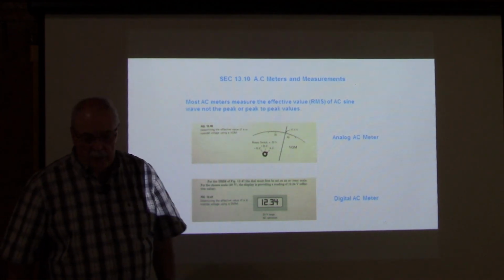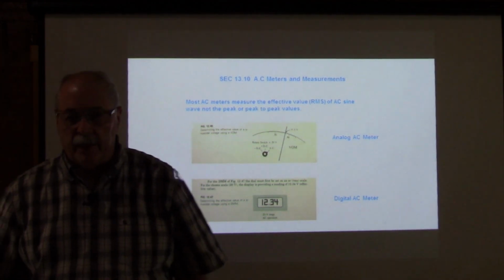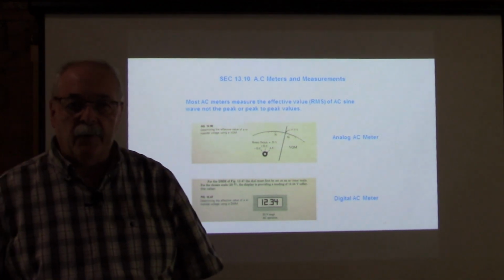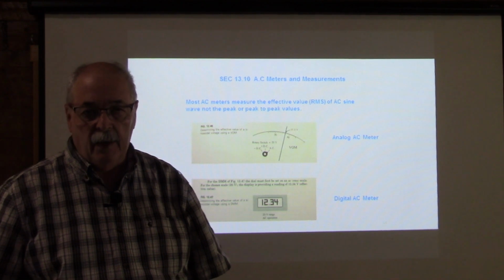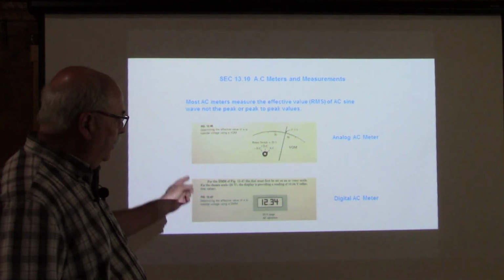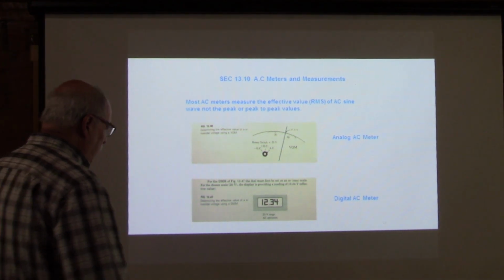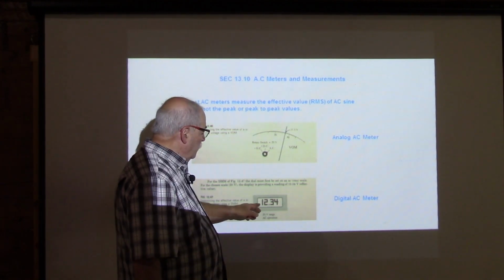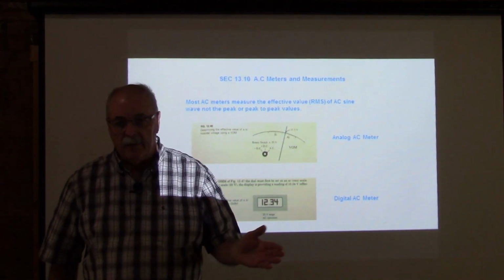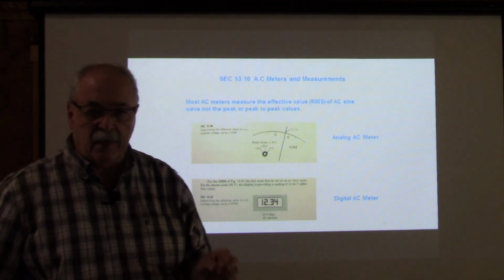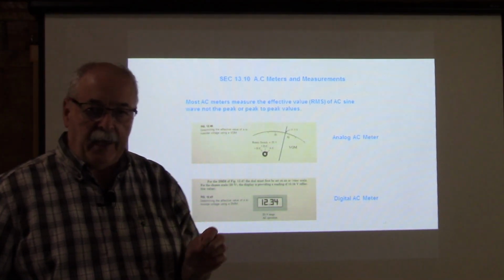So we use it in our medical equipment, for the output of electrical stimulators that people use for physical therapy. If you connect it, you'll read the same output down here, but if you were to move the amplitude adjustment up and down and there's something wrong with it, say a dead spot or a spike, you'll never see that, but you'll see it here.